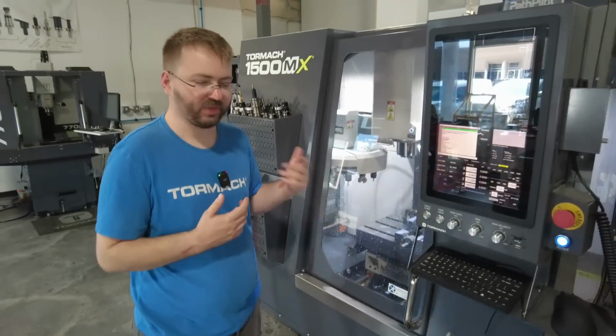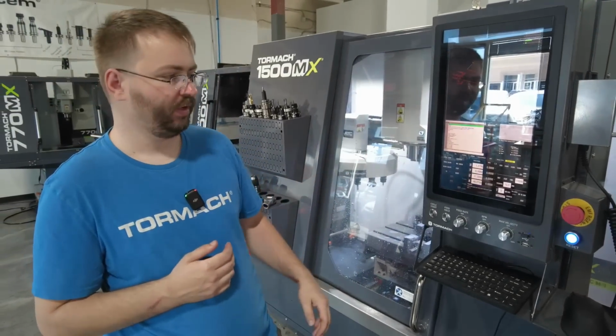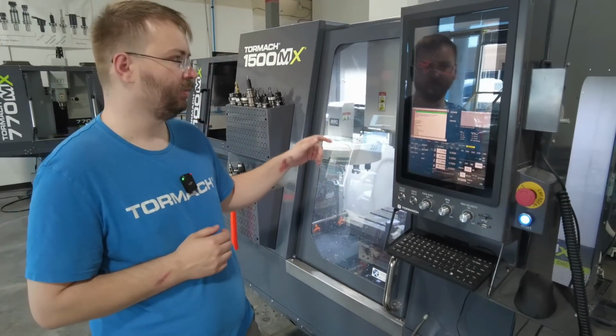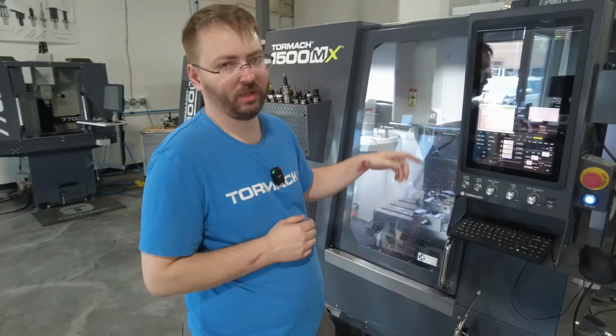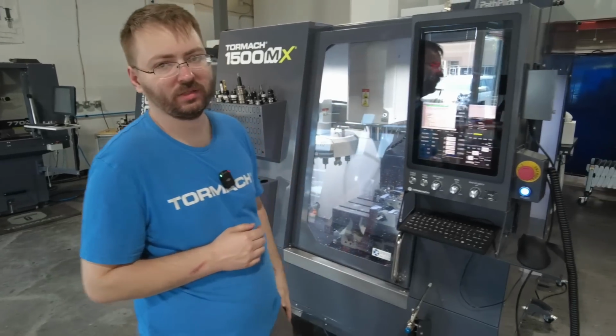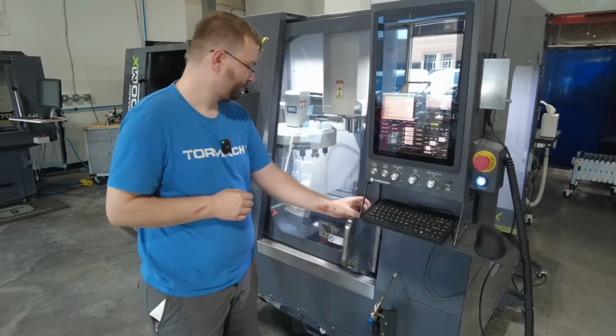You'll get a pop-up saying align those 2 marks. You press OK, and then we're going to rotate and find the nearest index pulse of the encoder and back it up. So you only need to be within about 5 degrees by manually aligning it — everything else is handled by the homing routine. That'll hold it until we re-reference them or pull off the A-axis; otherwise, it'll still be referenced.